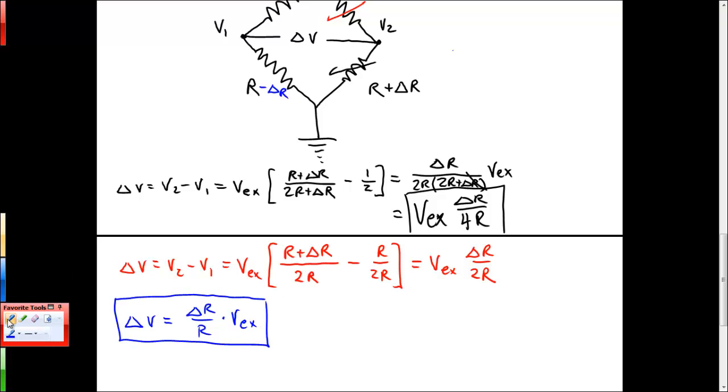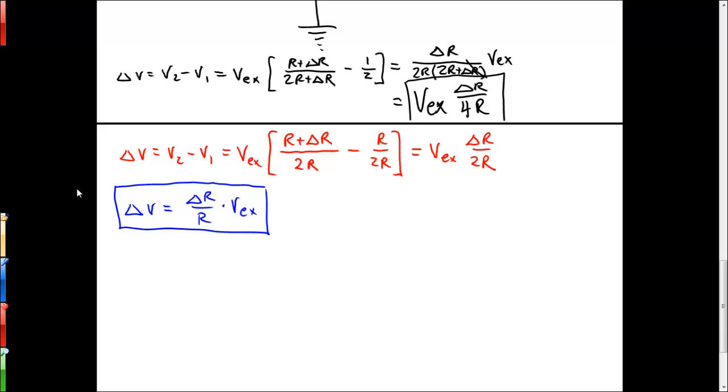So let's go back to the case where we had just the two strain gauges and work through a short example. In this case, we know that delta V is equal to the excitation voltage times the change in resistance over twice the nominal resistance. We can write this as excitation voltage over 2 times delta R over R.